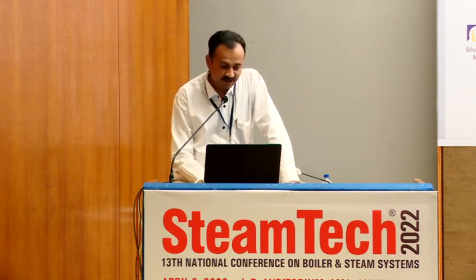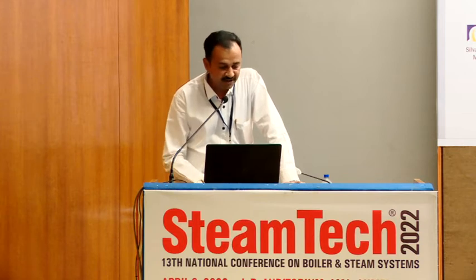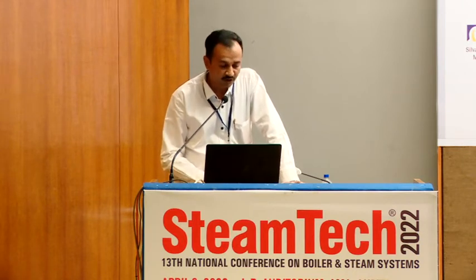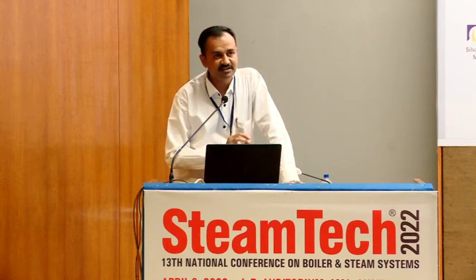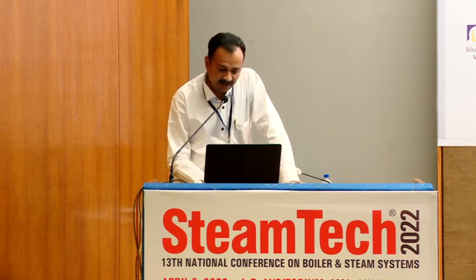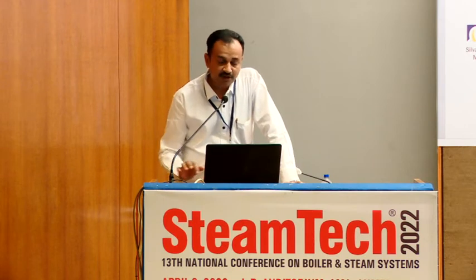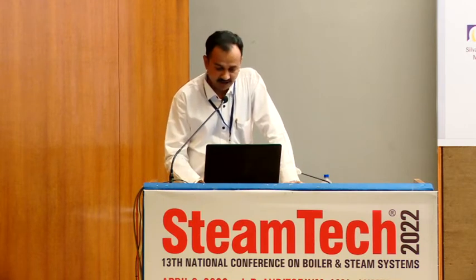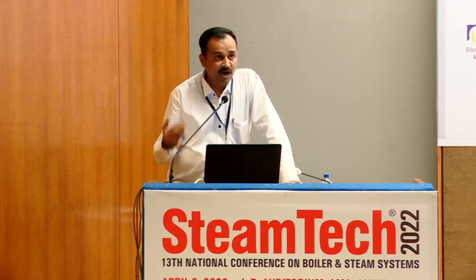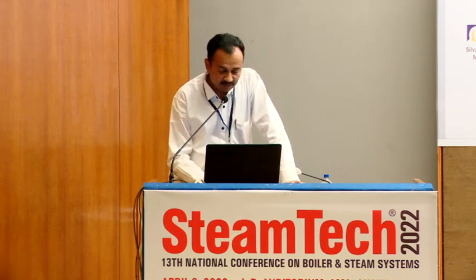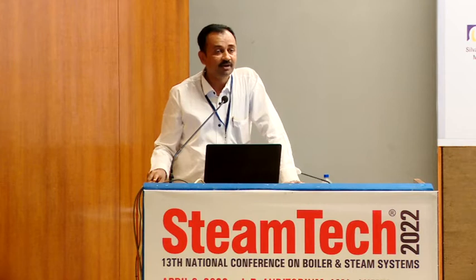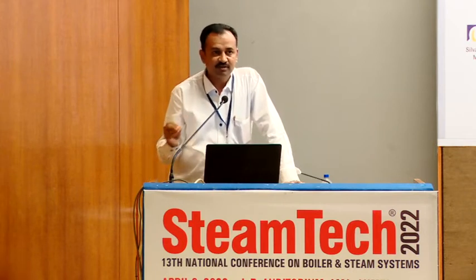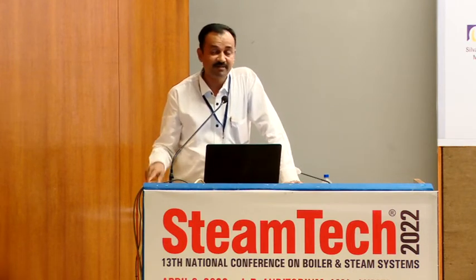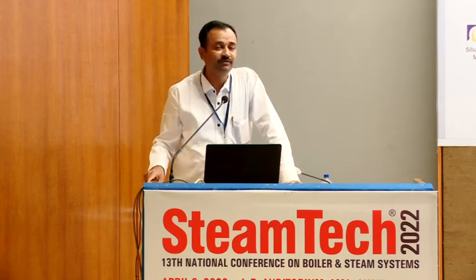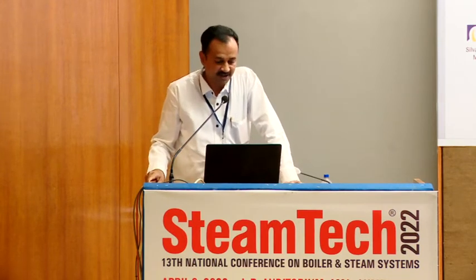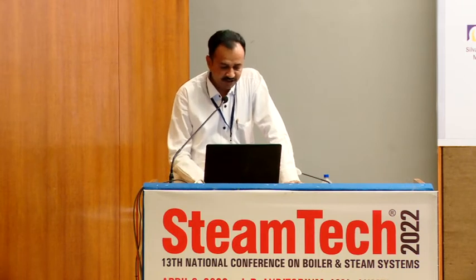For these 16 customers, you can see the temperature, flue gas temperature, ambient temperature, combustion parameter, fuel flow and steam flow, all connected. Green means it's 100% up and running. And if you take the average, the uptime is in the tune of 92 to 95%. So that is how we sustain the uptime: not just denoting the uptime, but giving the best suggestions to maintain it, and to utilize the uptime to further improve boiler efficiency and safety. So this is what we can do.